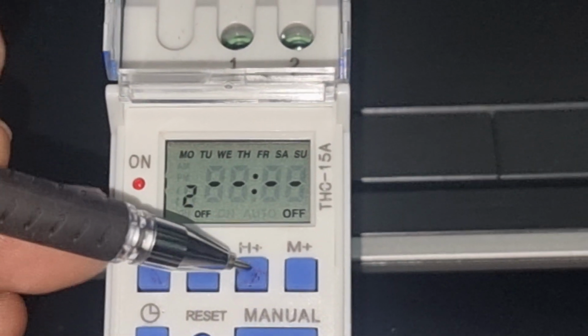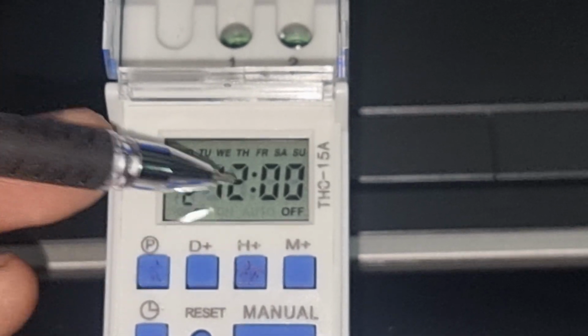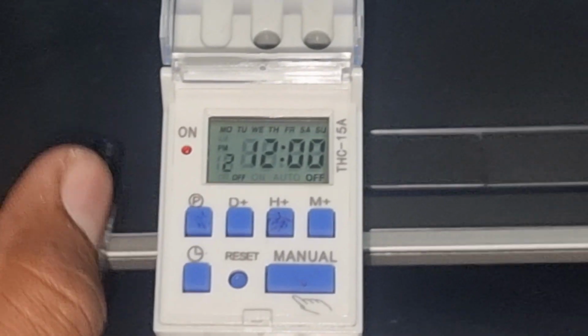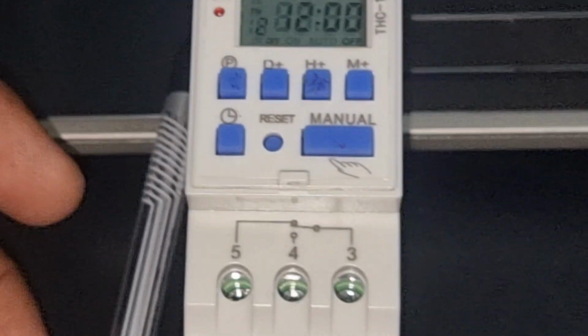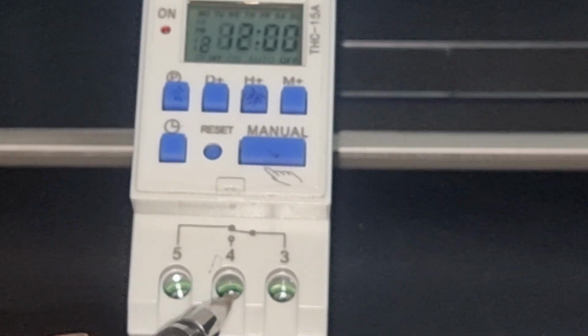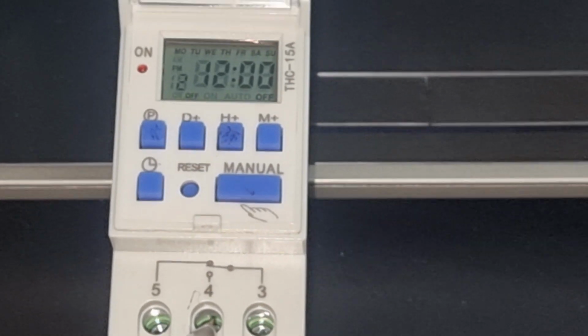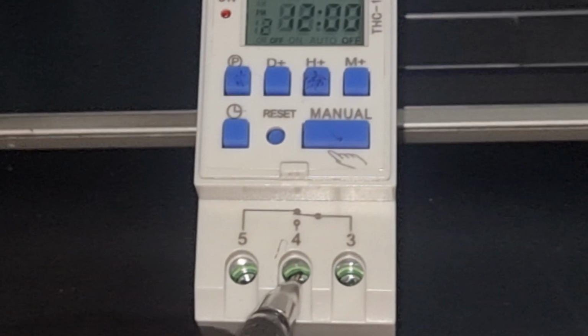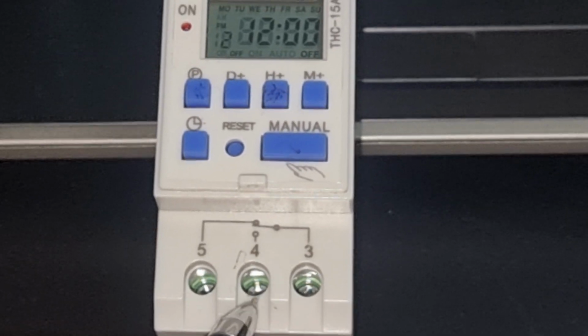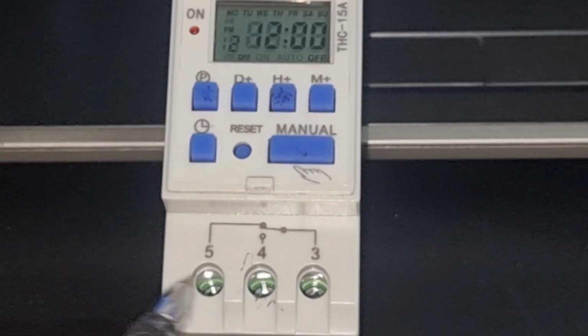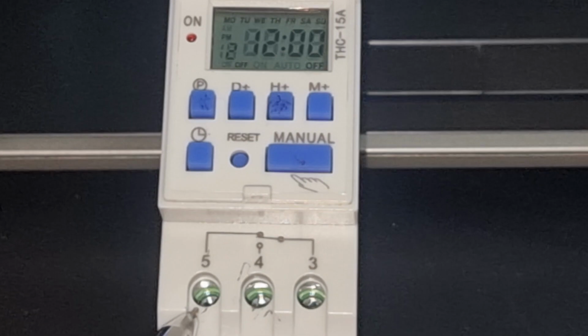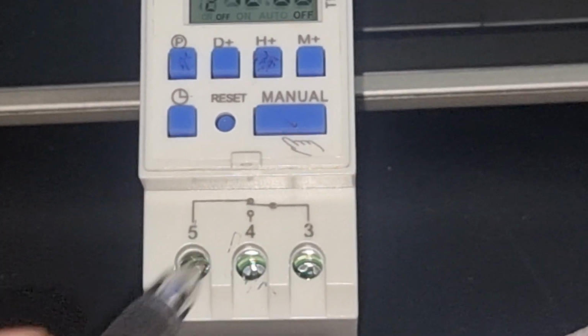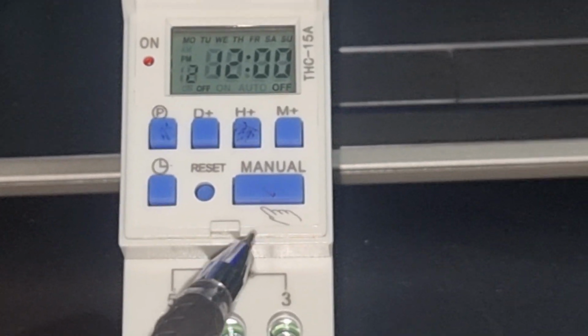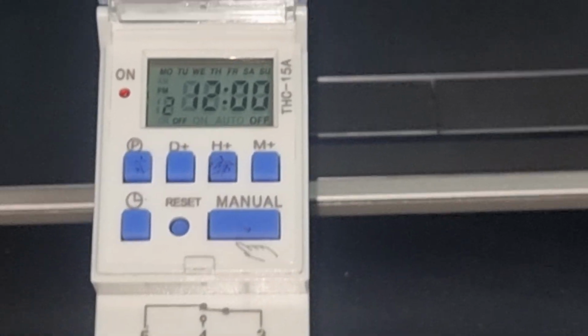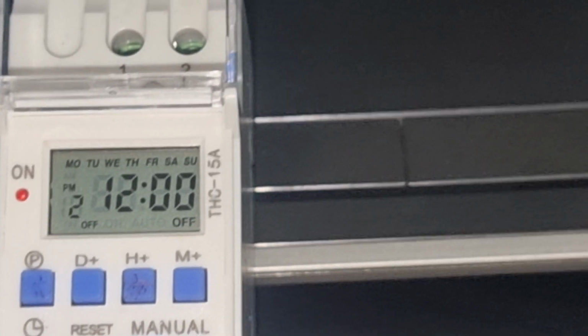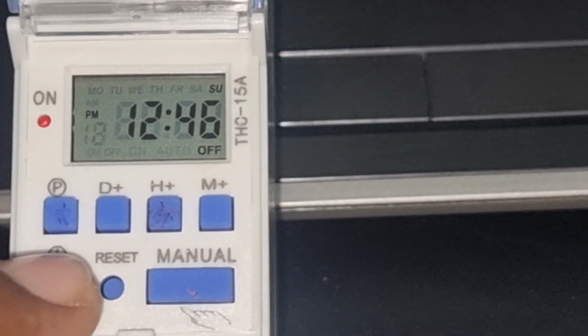Then press P, and at 12 p.m. it will turn off. So what is the meaning of this? It will run from 6 a.m. to 8 a.m. on point 4, which means pump number 1. From 8 to 10 this one is off, so pump number 2 will run on point number 5. So for one duty, one standby, whether the timer is on or off, it will run one of the pumps. We set it to 2, then we go to time, and it is done.